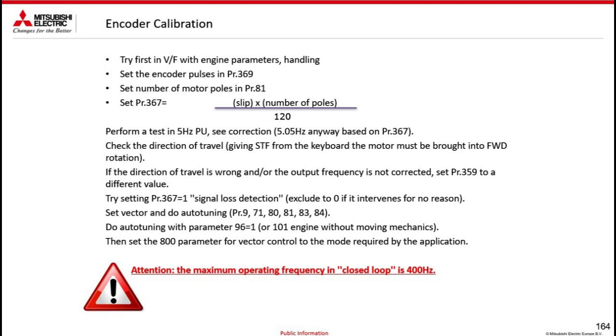So I put the inverter in V on F mode, and then I modify parameter 369, where I must put the resolution of the encoder. In parameter 81, the number of poles of my motor, and in parameter 367, I perform this calculation: nominal speed minus real speed, times the number of poles, divided by 120. Once this is done, I run a test in PU, for example, at 5 Hz.